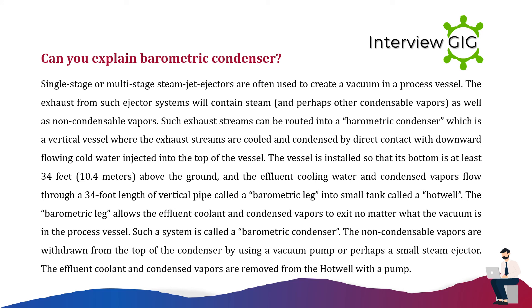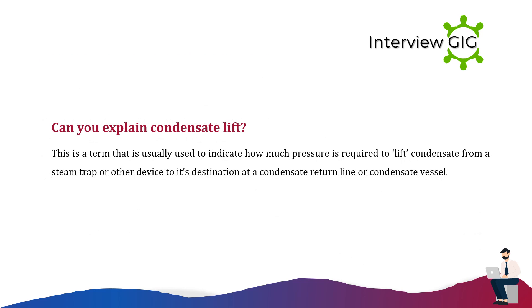Can you explain a barometric condenser? Single-stage or multi-stage steam jet ejectors are often used to create a vacuum in a process vessel. The exhaust contains steam, condensable vapors, and non-condensable vapors, and can be routed into a barometric condenser — a vertical vessel where exhaust streams are cooled and condensed by direct contact with downward-flowing cold water injected at the top. The vessel bottom is at least 34 feet (10.4 meters) above the ground, and effluent cooling water and condensed vapors flow through a 34-foot barometric leg into a small tank called a hot well. Non-condensable vapors are withdrawn from the top using a vacuum pump or small steam ejector, and effluent condensate is removed from the hot well with a pump.